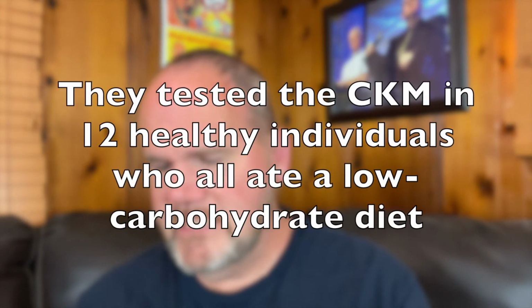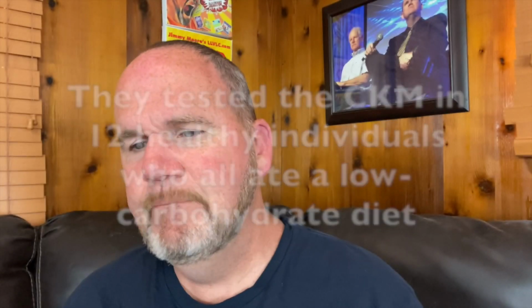The methods they used for this: a continuous ketone monitor sensor was developed, and the technology is called wired enzyme technology. And what it looks for is beta-hydroxybutyrate dehydrogenase, and it uses that chemistry to test in the interstitial fluid. In vitro characterization of the sensor was performed in phosphate buffered saline at 37 degrees Celsius. In vivo performance was looked at in 12 healthy participants, all eating a low carbohydrate diet. They wore 3 of those sensors at a time. So they had 3 ketone sensors on the back of their arm, and they continuously measured their ketone levels over a 14-day period.